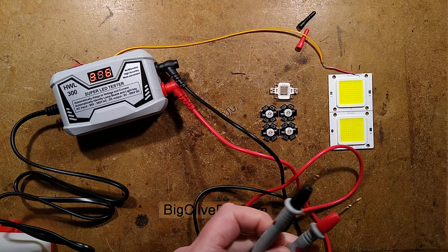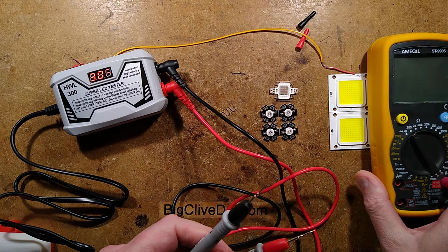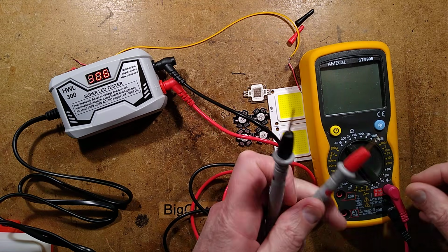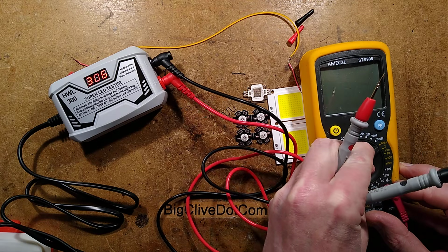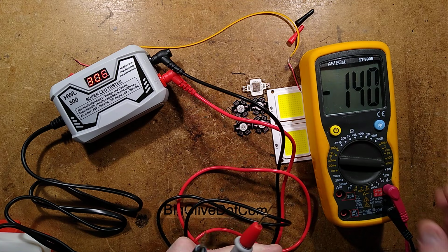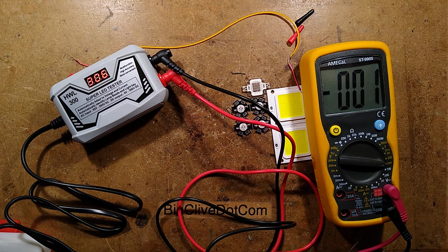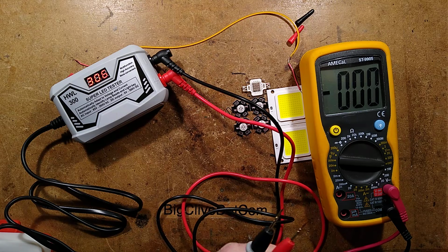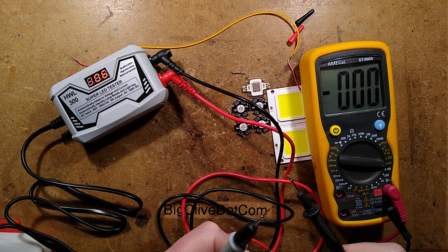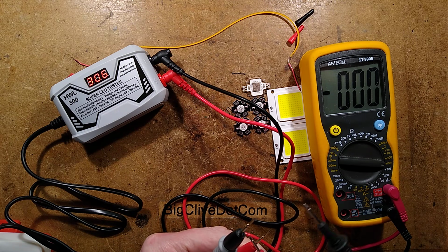Let's actually test the voltage - let's get the meter onto this. So I shall set this to 1000 volts DC, and we'll stick the probes on and see what it reads, and see if it changes the other reading, because there may be an impedance thing involved here.